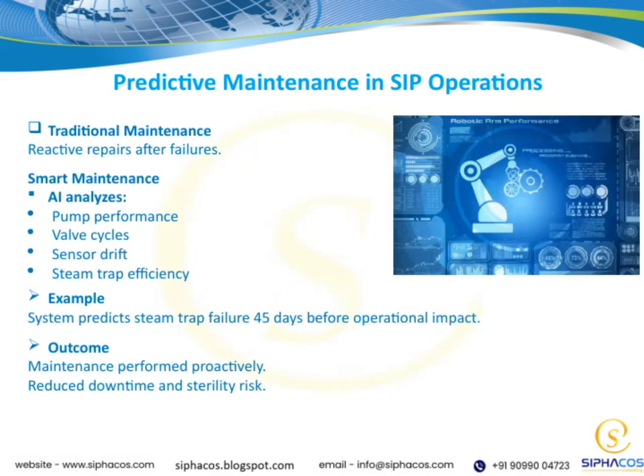Let's talk about predictive maintenance in SIP operations. Traditionally, maintenance happens reactively — we fix things after they break. But smart maintenance flips that on its head. Here, AI steps in, analyzing pump performance, valve cycles, sensor drift, and steam trap efficiency. For example, the system can predict a steam trap failure 45 days before it affects operations. That means maintenance gets done proactively, cutting downtime and lowering the risk to sterility. It's a smarter, safer way to keep things running smoothly.